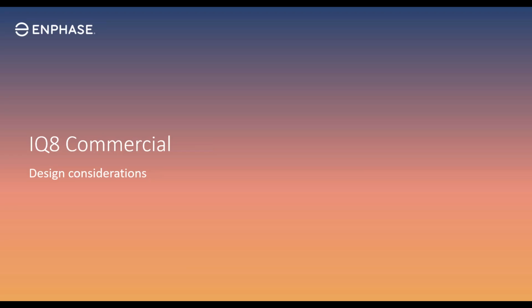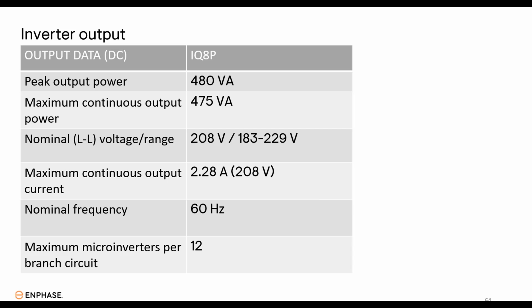Let's get into some design considerations for the system and design constraints. Because the Enphase commercial microinverters use reactive power, its output power is measured in volt amps. The max output power is 480 volt amps for the IQ8P 3P microinverter. The max continuous output power is 475 respectively. The nominal voltage range is 208 with a max output current of 2.28. The maximum number of microinverters per branch circuit is 12.